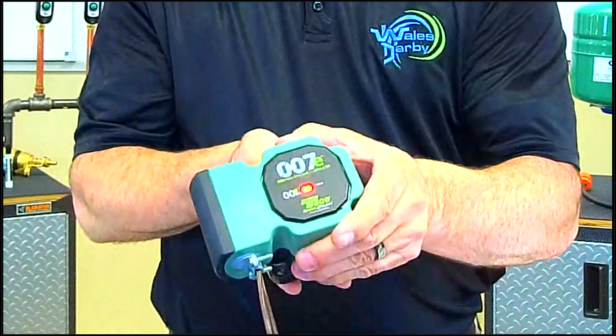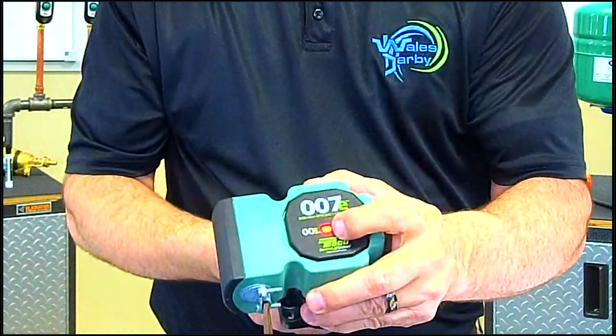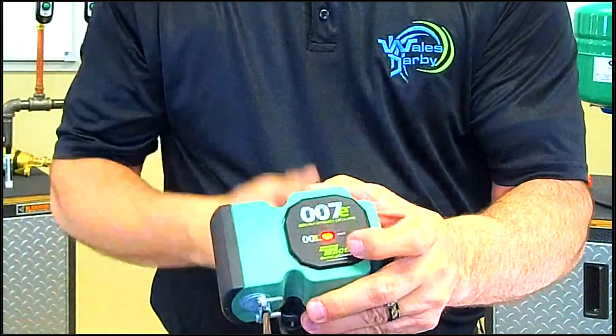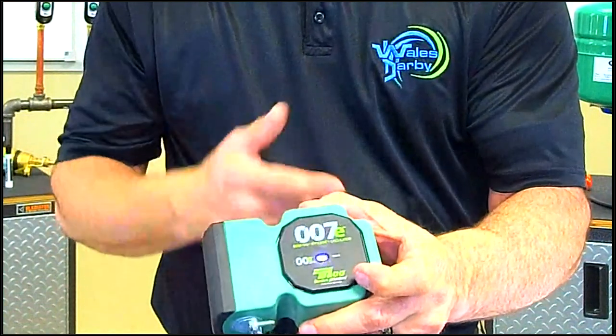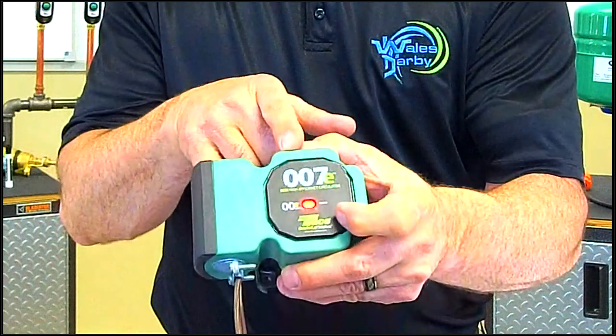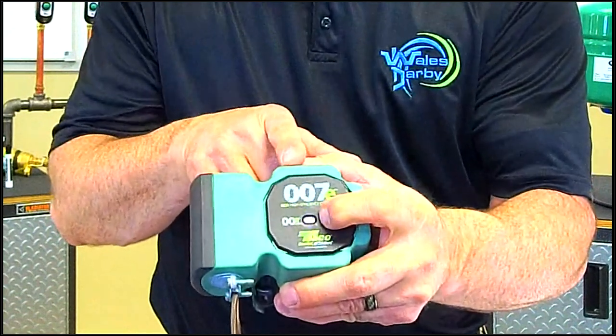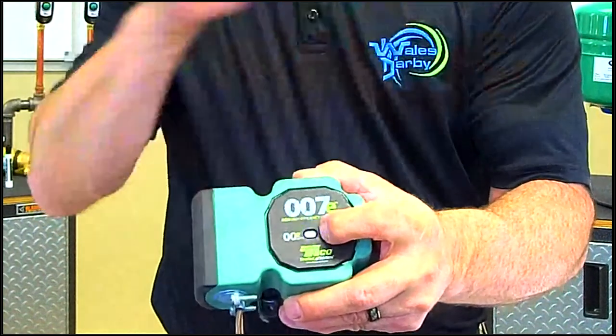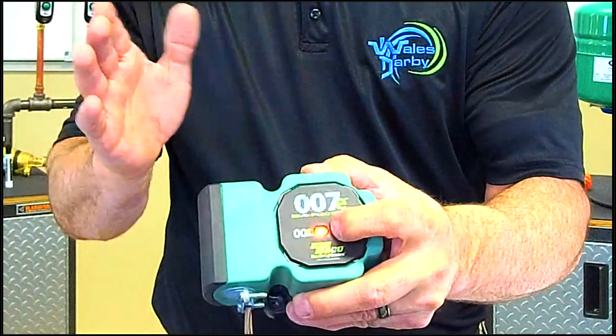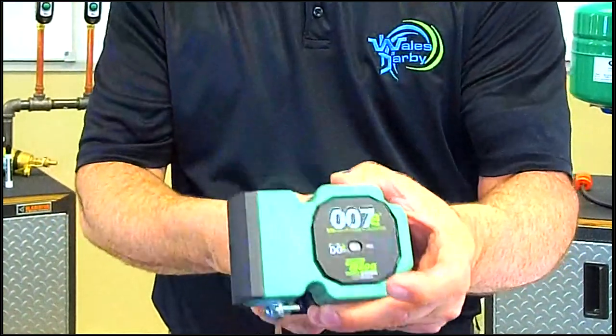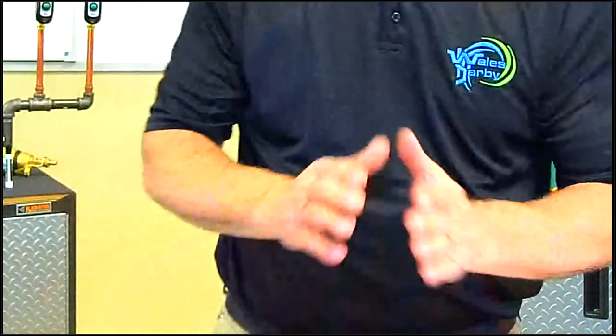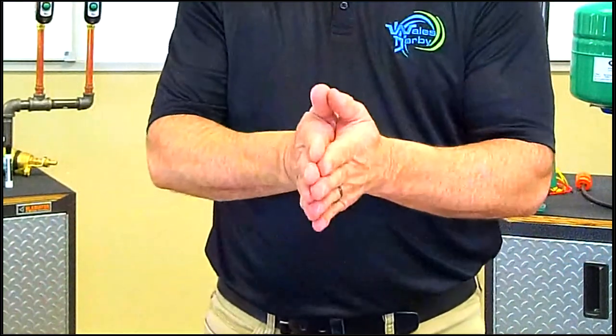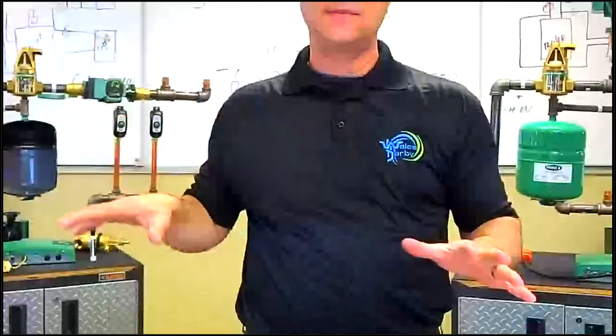And the whole time it's doing that, it'll be flashing white. I don't have my hand on it right now, but it's recognizing that there's no resistance. So it's flashing white. It's trying to purge the air out. And if we left this on, it would eventually go to red. I don't want to burn it out, so I'm going to have Eric unplug it. This will all go on at the home. You may not even have to be there. This will save you a service call over the life of that circulator.